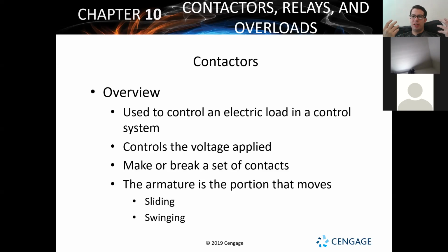With power present in the system while we're testing a contactor, we cannot have our meter set to resistance or ohms. If we set our meter to resistance or ohms and use it on a system that has power passing through it, that will destroy your meter. It will damage it very, very badly. So if there is power present, do not test with resistance. For the contactor, what we're going to test is voltage. There are a couple of different things we're going to see with voltage as far as switches are concerned and how they operate.